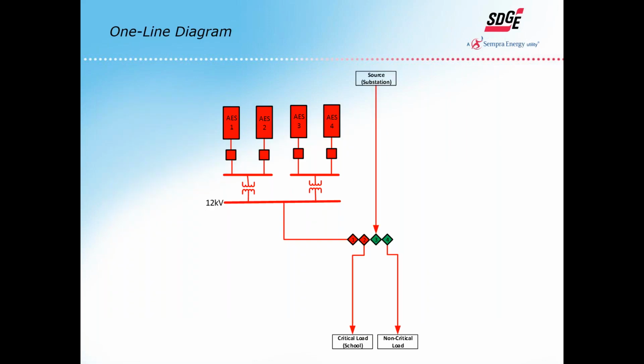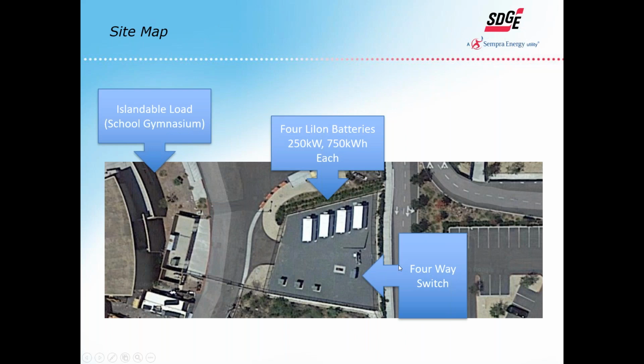So here's a one-line diagram to show what is electrically connected on our system. This represents the energy storage systems. You can see our transformers get our power up to 12 kV, like the rest of SDG&E's grid, and this is the critical piece here, this 4-way switch shown here.